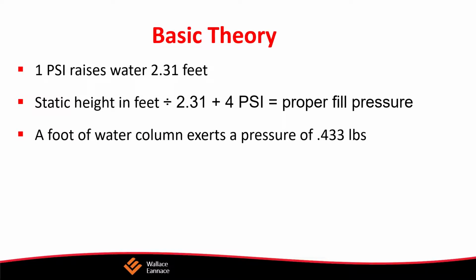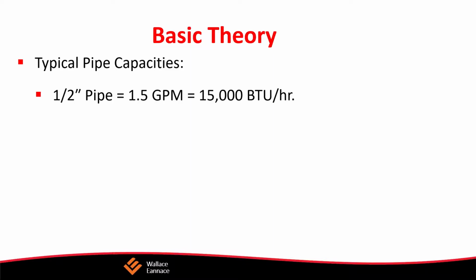And similarly, 1 over 2.31 is going to be 0.433 pounds. So a foot of water will exert pressure of 0.433 pounds. The rule of thumb when sizing the maximum flow rate that will fit through a pipe without making velocity noise: the pump head will be 4 feet for every 100 feet of pipe. Okay, that's a key thing. When you're sizing a pump, the maximum flow rate that will fit through the pipe without making velocity noise, the pump head will be 4 feet for every 100 feet of piping. So if we take typical pipe sizes, a 1/2 inch pipe will flow about 1.5 GPM.